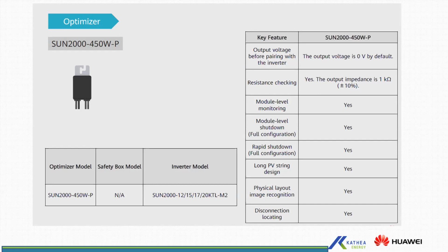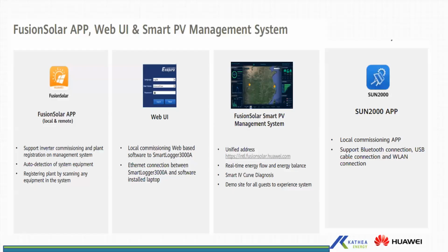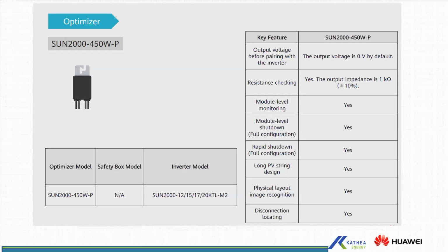So basically, the optimizer technology is there to enable you to have maximum power point tracking for your modules. That is at module level. It gives you module level monitoring. It enables you to have long string design. It also helps for protection in case of your inverter faults or your inverter is off. When the inverter is off, the optimizers will actually tap down the voltage to 0 volts. That is safe working voltage to avoid fires and all that in cases of arc fault. So we have a session where we'll also touch in detail on the optimizer when we get to our residential range.